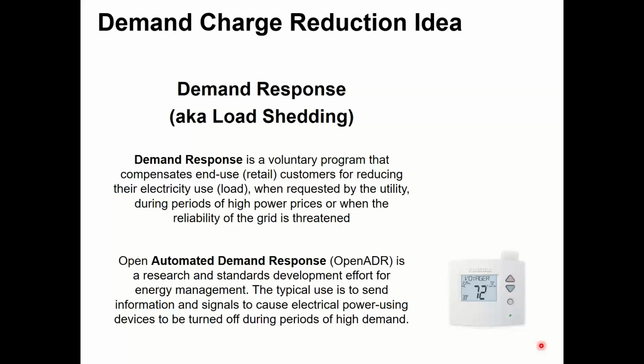But for small buildings, which are the kind that have package systems, we can't contact every building operator and tell them that. So what ends up happening is you have technology taking care of that. One way to do that is through the thermostat, in what's typically referred to as an open ADR, automated demand response. The utility sends a signal to the thermostat and tells the thermostat, "Hey, we're in a demand event today from 2 to 4 p.m. Can you do something about that? Can you spread your set points a couple degrees? Instead of cooling your building down to 73, why don't you only cool it down to 75, right? And we'll pay you something for that. We'll give you either for that event or for that to be part of that program."